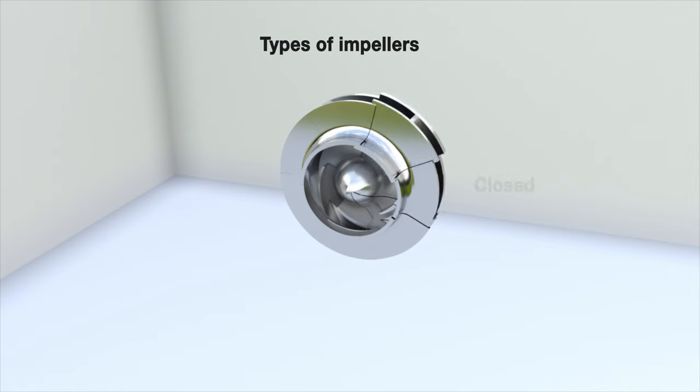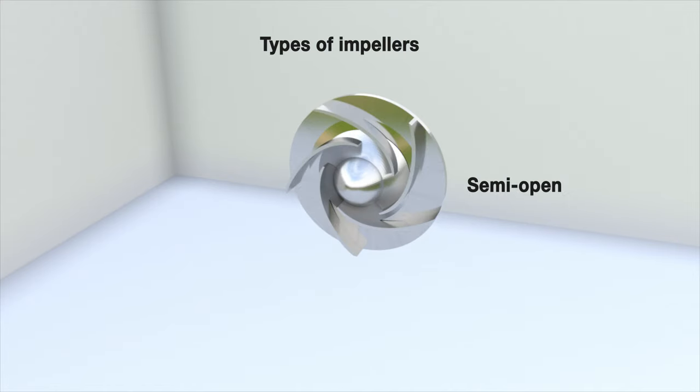Three main types of impellers are used in centrifugal pumps. Closed with back and front discs, vanes and fairings. Semi-open with the vanes free on the front side. Open with the vanes free on both sides.